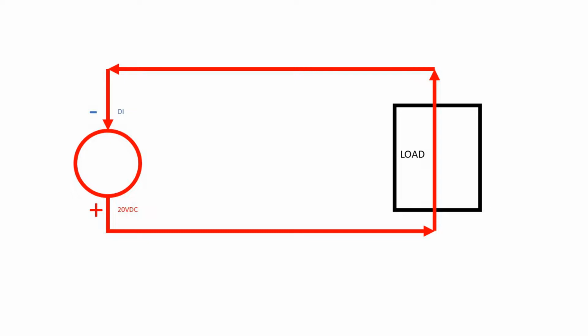If you close the same contact, the circuit closes and there is the full flow of your current throughout the circuit. It is generally a DC voltage, according to how the controller is manufactured, a minute DC voltage which is being fed, which has to flow through the loop and come back so that it recognizes, okay, the loop is complete, and that is considered as one. So zeros and ones are being fed with a contact which is open or which is made. Once you have an open contact, that's considered zero. Once you have a made contact or a normally closed contact, that's considered a one.